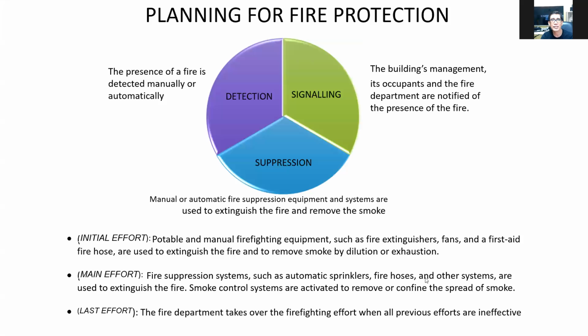Planning for fire protection, we have detection, signaling, and suppression. The presence of fire is detected manually or automatically. That is one, you need to detect. If there is a fire, you need a fire alarm, smoke alarm or heat alarm. Another one is signaling. If there is a fire, you should have a way to signal it.